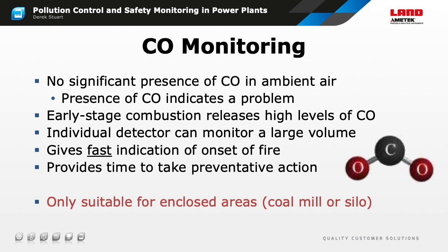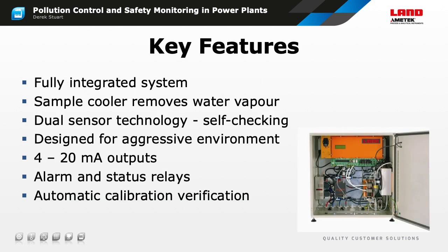An alternative to a level alarm is a rate of change alarm. This type of alarm ignores the background level of CO, but responds to the rapid increase that's associated with early stages of spontaneous combustion. I'd just like to emphasize the point at the bottom of the slide. CO monitoring only works in enclosed spaces. Open areas such as storage piles and conveyors have too much air movement, so any CO is carried away as soon as it forms.